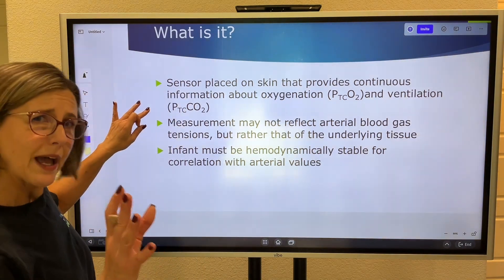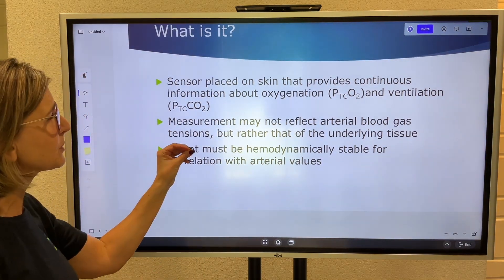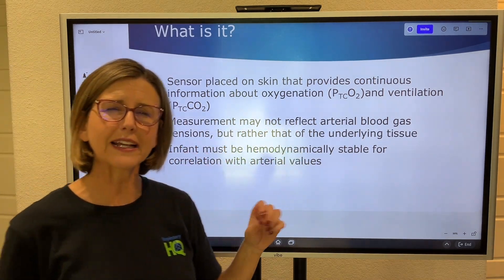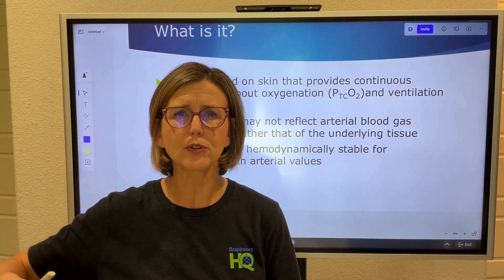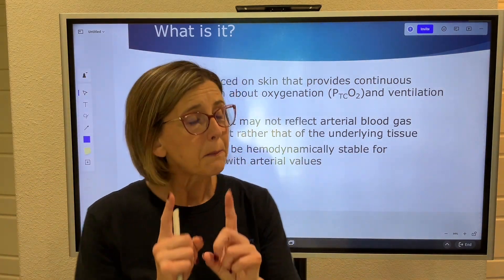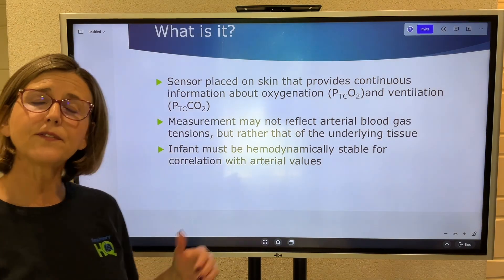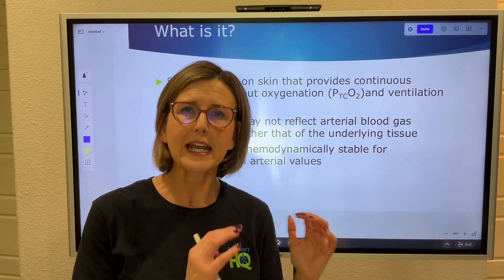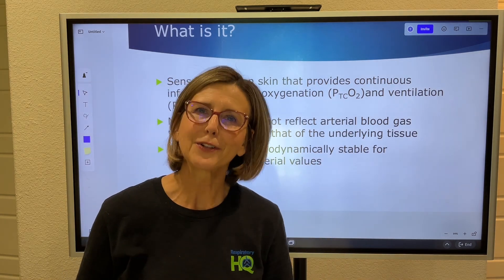One important thing to remember: this measurement may not reflect arterial blood gas tensions. It doesn't equal the PaO2 and PaCO2 exactly, because what it's measuring is in the underlying tissue. But as long as the infant is hemodynamically stable, there is a correlation between the two.